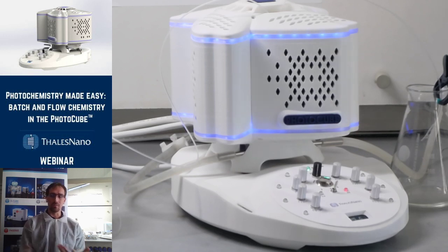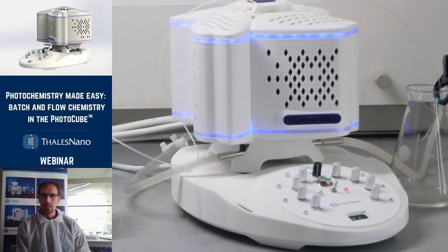We don't supply just a couple of vials with the PhotoCube. These are standard vials. So if you want to pressurize the vials, you need to buy special vials which can be pressurized. Otherwise, if you don't want to pressurize your system, you can just use simple screw cap vials. Can we do pressurized reactions? In batch, you cannot really do pressurized reactions, except if you ensure that you have pressure vessels for that. In flow, you can hook up the tube or the loop to a back pressure regulator, and then you can pressurize your system.